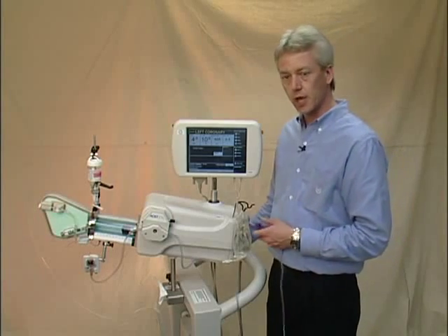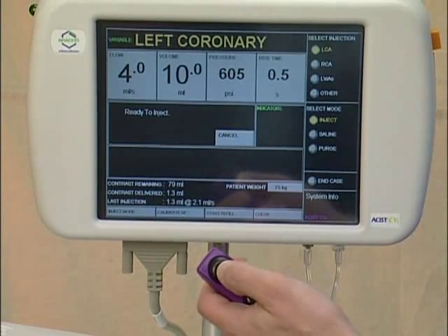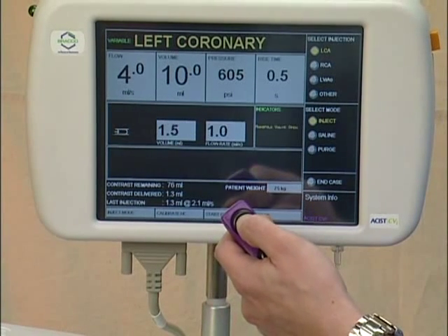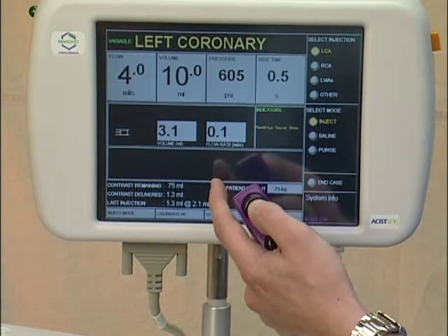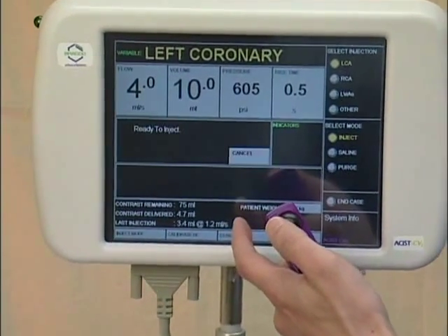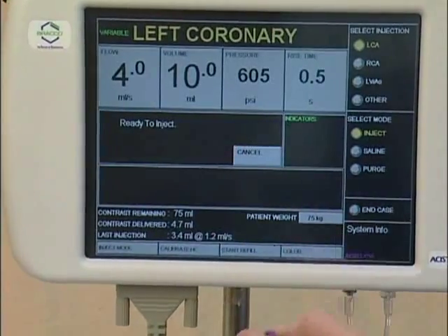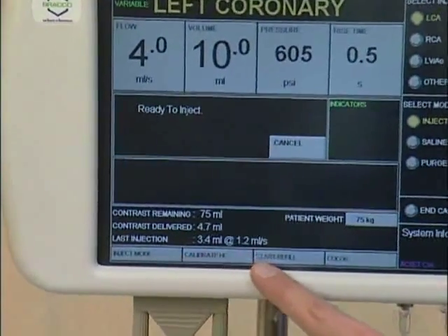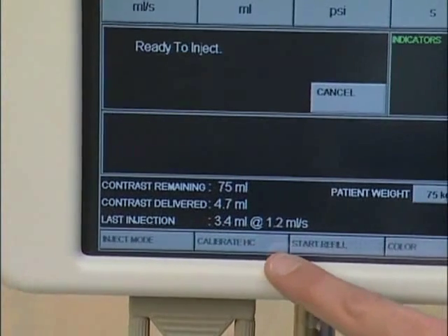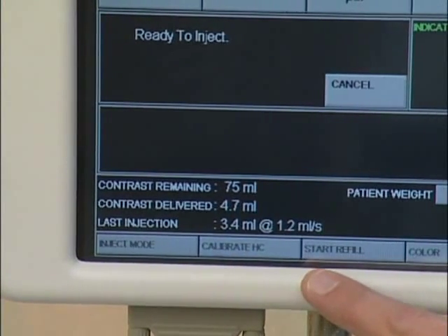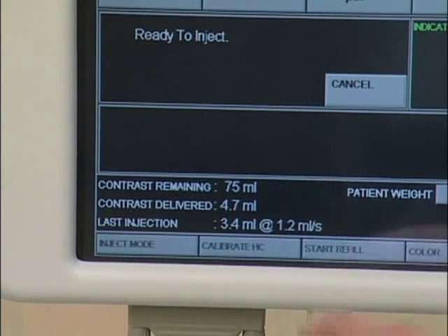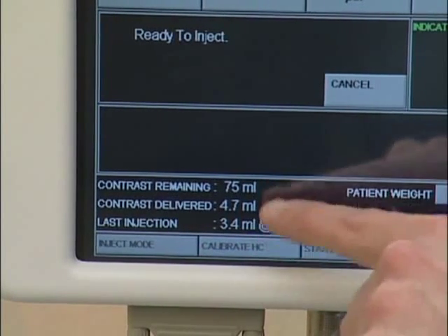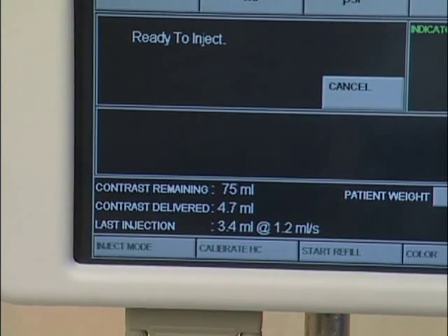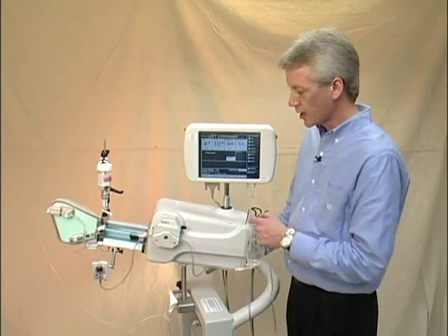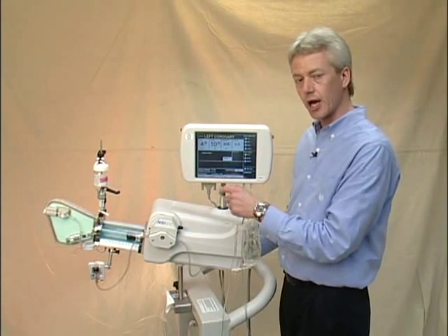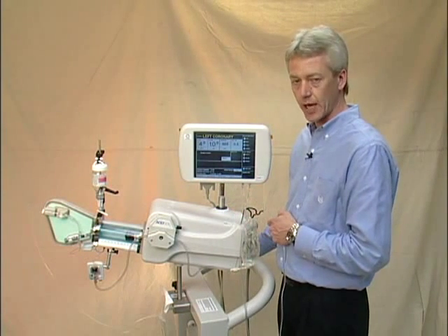To perform the injection, the operator will simply press on the top contrast button, and as you can see, as I perform the injection, you receive a real-time flow rate and volume that is being delivered. After the injection is complete, you'll see under the last injection area the actual flow rate and volume that I achieved for that injection. Along with the other information at the bottom, you see a contrast remaining total and a contrast delivered total. The contrast delivered total helps the operator determine how much contrast was delivered to their patient during that procedure.